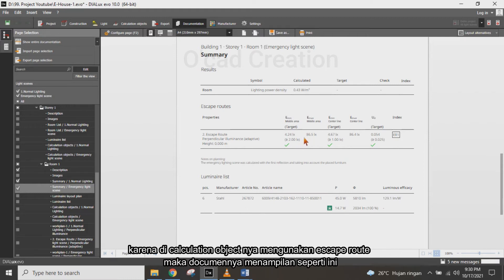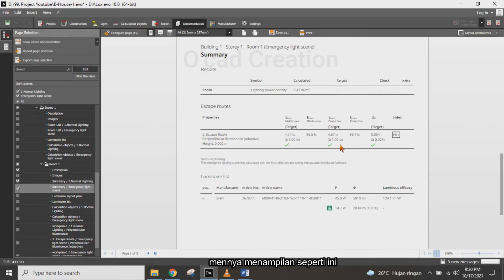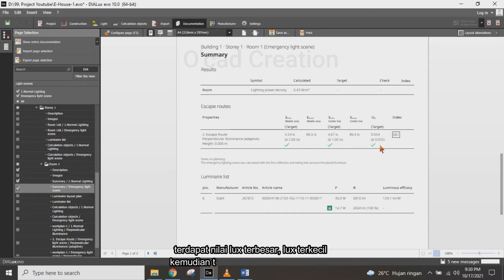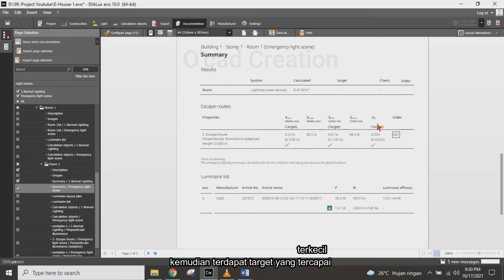Below there is a description for the building, similar to the normal lighting summary. Because the calculation object is used for an escape route, the document shows the lux minimum, lux maximum, and the target value.